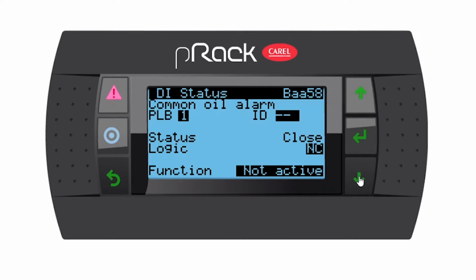Let's go down. Do you have a common oil alarm? If you do, assign it. A liquid level alarm. Yes, we do have one. So I'm going to assign it to U5 or input 5. Normally closed. If we go down, fans common overload. Do you have one? If you do, assign it. Heat reclaim. Do you have it? If you do, assign. We've got generic function F, G, H, I, and J. Those are all your generic functions. If you are using a generic function, you have the option for a digital input for that generic function. Do we have a unit on-off status? If you do, you have the ability to assign it. A pRack working status. And then we're back at the beginning, common low pressure stat. So now I've assigned all my digital inputs.